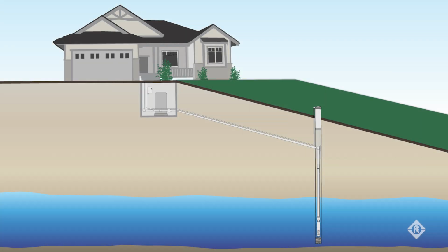Let's take an example of a pump for a 3-bedroom house with a well that has a flow capacity of 15 gallons per minute. With this information, we usually suggest a 10-gallon-a-minute pump, which will have to produce 10 gallons a minute at pressure from lower than static level. The 15 gallons per minute would have been established from the driller's log if we're installing a new pump and well.